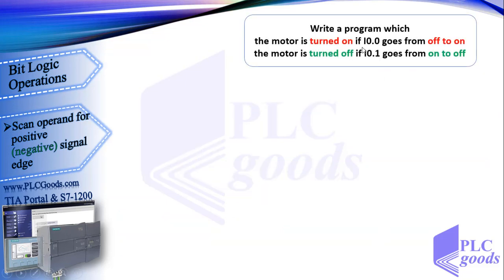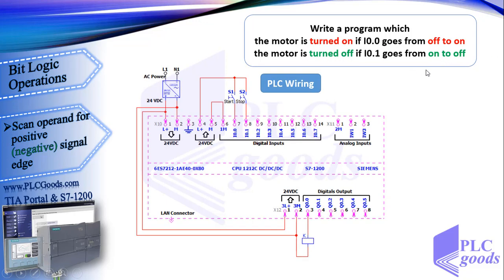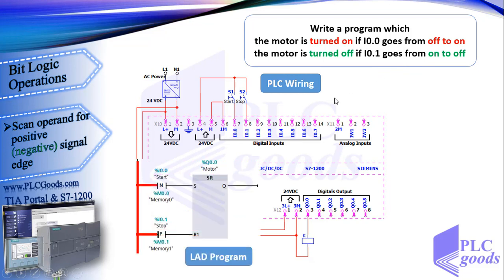Let's write a program which turns on a motor when I0.0 goes from off to on, and turns it off when I0.1 goes from on to off. We've written a motor program before, but now we want it to work based on changes in pushbutton states. This is my program with an SR flip-flop. To set the output, I use the instruction which scans I0.0 for a positive signal edge.